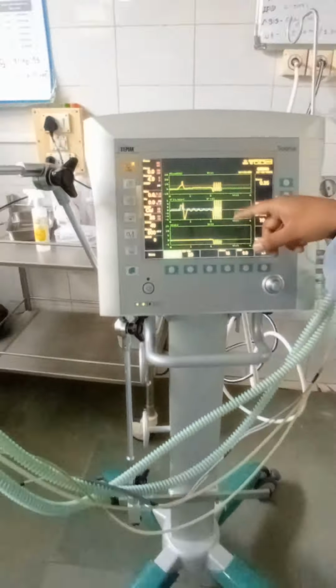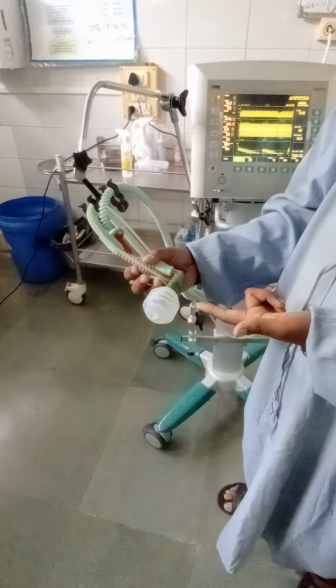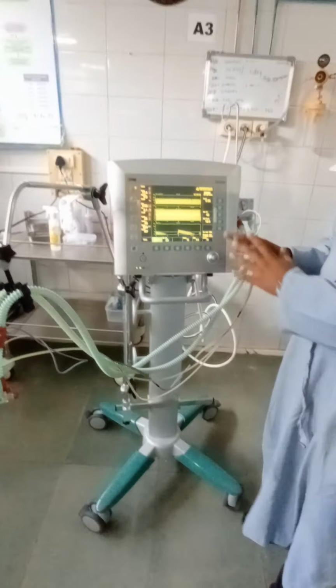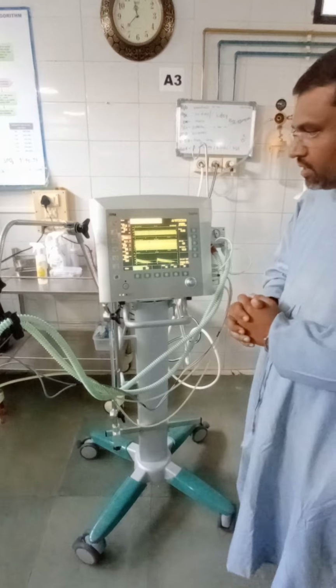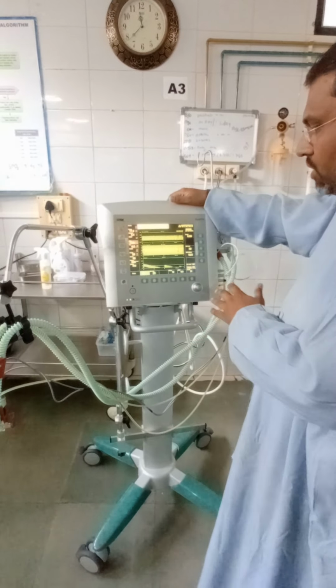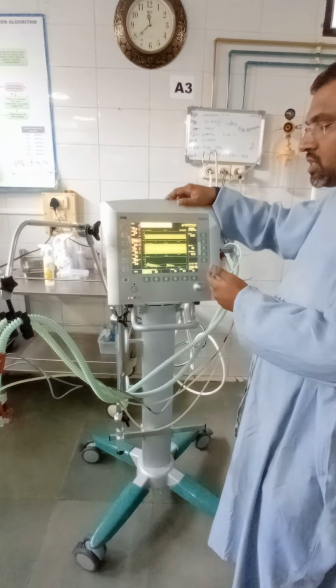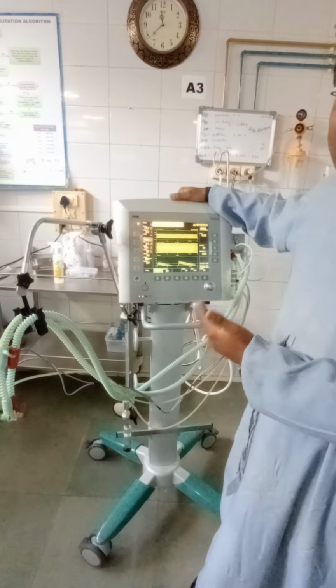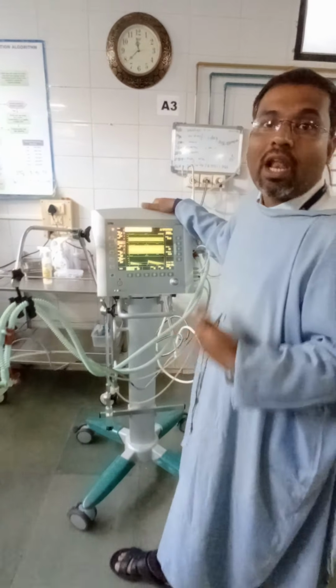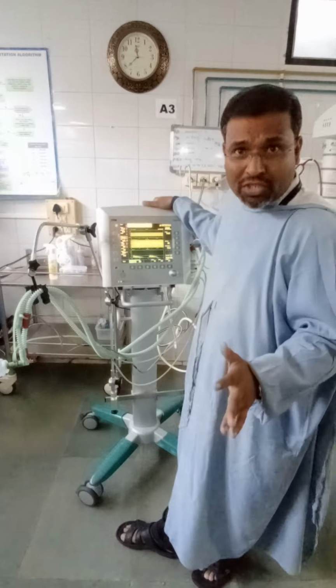Now you can observe this is nothing but HFO started. You can observe the test lamp. See, that means there is no error on the machine. That means your machine is working properly, right? Now one more thing. Sometimes what happens is, due to improper alarm limits, the machine is giving alarms continuously. There is no issue inside the machine, right?